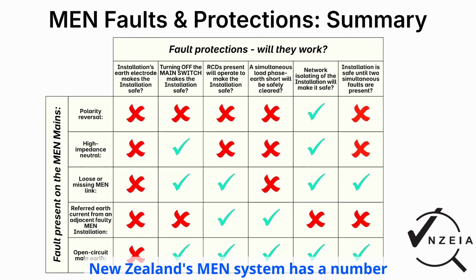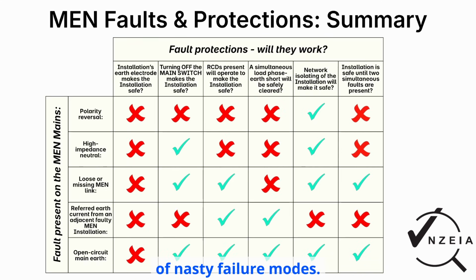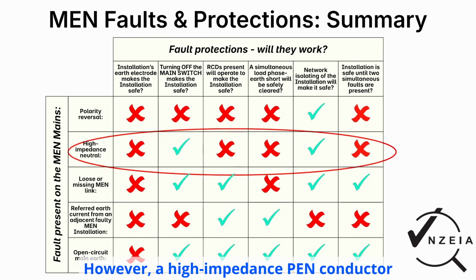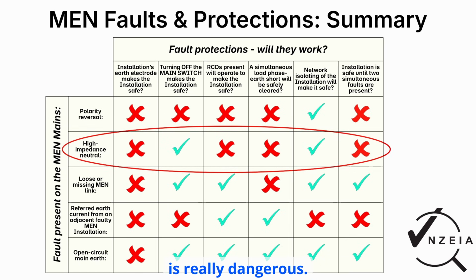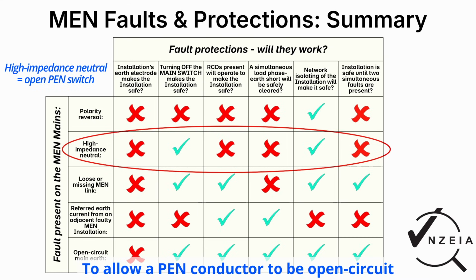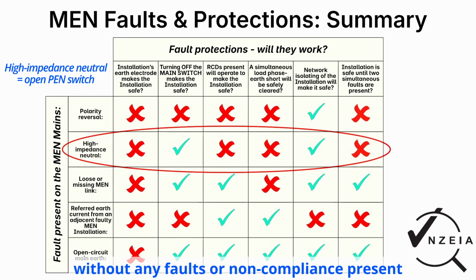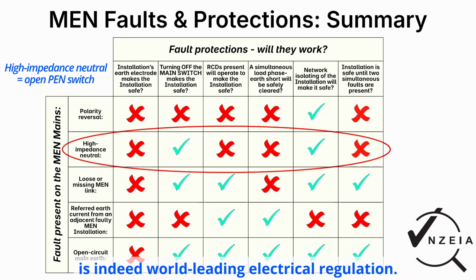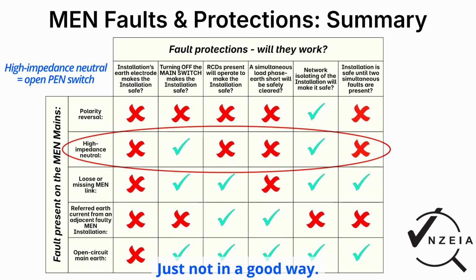New Zealand's MEN system has a number of nasty failure modes. However, a high impedance PEN conductor is really dangerous. To allow a PEN conductor to be open circuit without any faults or non-compliance present is indeed world-leading electrical regulation, just not in a good way.